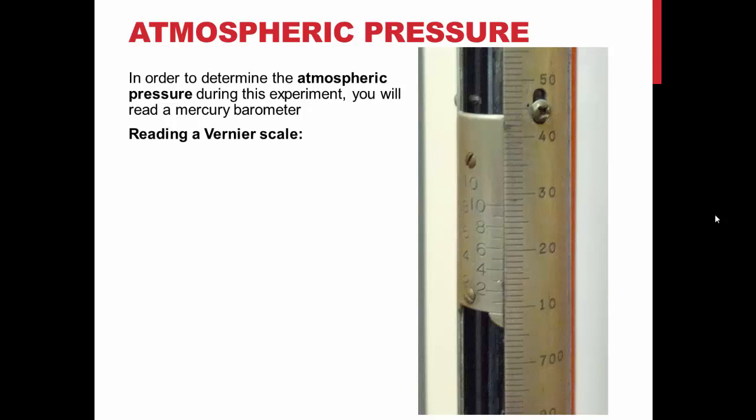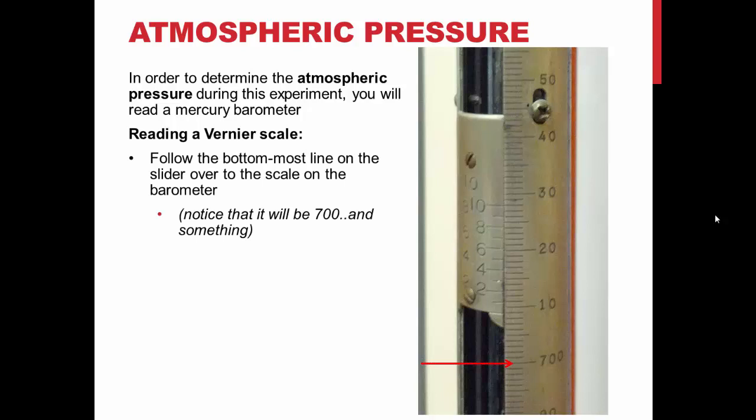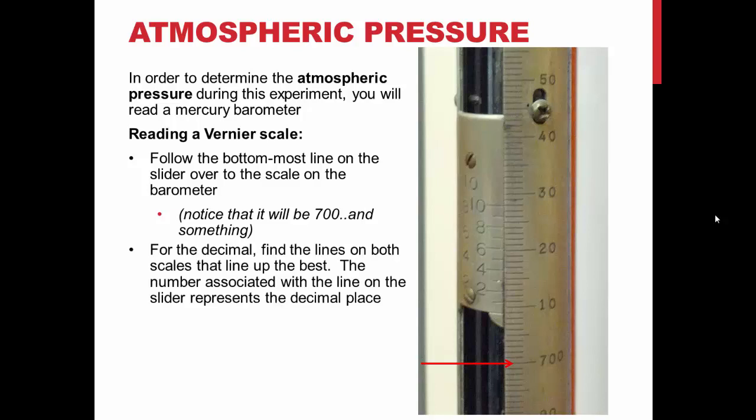Your first number will be read from the bottom of the scale, where the zero marker falls on the right-hand scale. In the picture shown, the zero falls between 708 and 709, making your first integer 708. This scale can be read to one decimal place, which can be found by looking to see which gradations on the right-hand scale line up best with the ones on the left-hand scale. In the picture, you can see that only the gradation for 0.9 lines up with any of the gradations on the right-hand side. This means your decimal place is 0.9, giving you an overall reading of 708.9 millimeters of mercury.